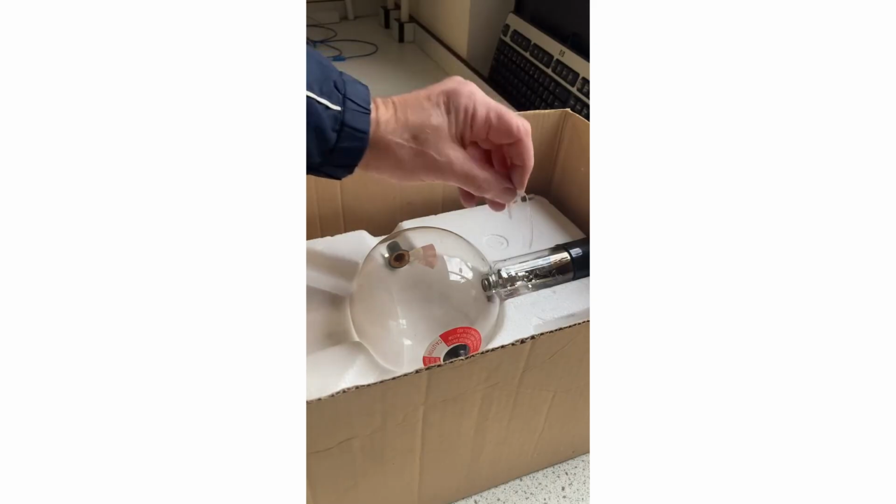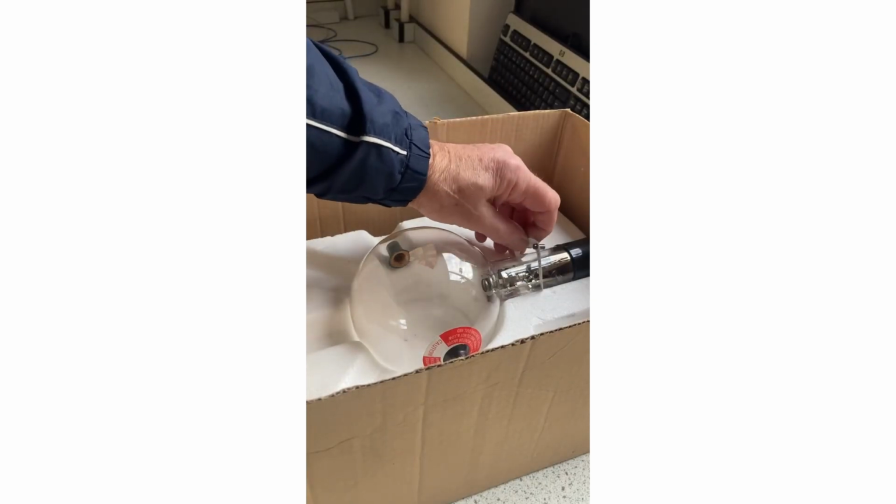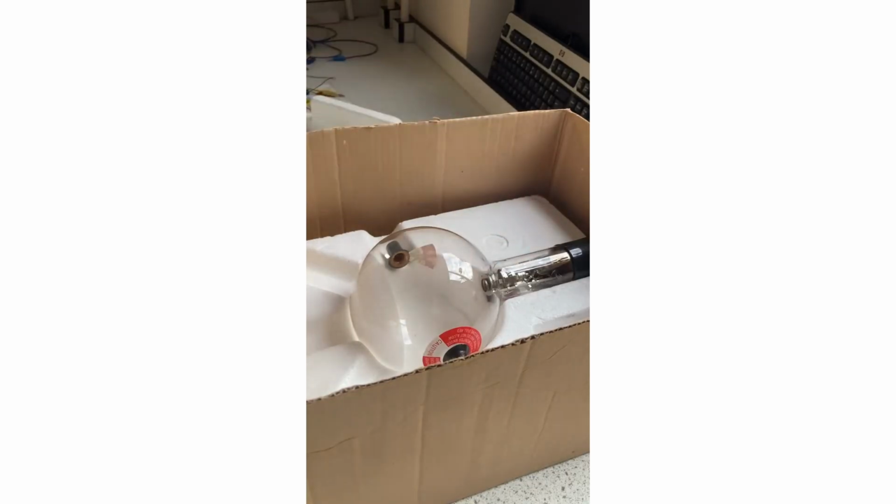Occasionally that whole graphite window will perforate, and the later ones of these were supplied with a little magnet on a collar that you can sit on the tube to deflect the electron beam slightly, to use a different part of the window. Now, I'm not going to connect that up and show you. Simon Polikoff has an excellent video on this.